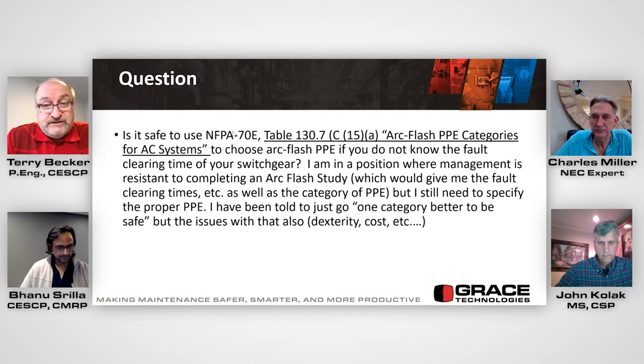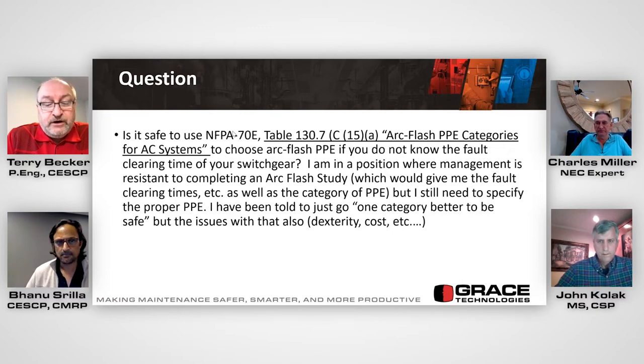But all that aside, 208 volt, three phase or higher, right? Minimum 8.0 calorie per centimeter squared, all the time, every time, or 480 or 600. Start there. Then use incident energy analysis or the table method to decide if you need an arc flash suit. And then I recommend a minimum arc flash suit of at least 75 calories, even 100 calories after that, as the standard.